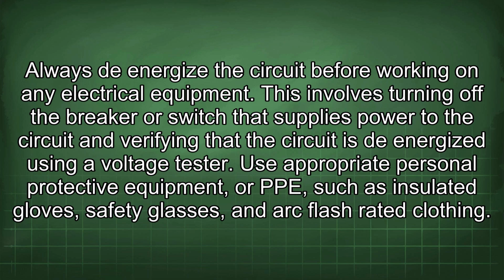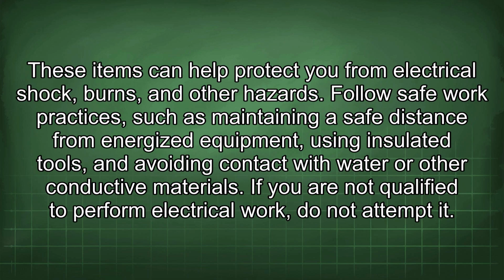Always de-energize the circuit before working on any electrical equipment. This involves turning off the breaker or switch that supplies power to the circuit and verifying that the circuit is de-energized using a voltage tester. Use appropriate personal protective equipment, or PPE, such as insulated gloves, safety glasses, and arc flash-rated clothing. These items can help protect you from electrical shock, burns, and other hazards.